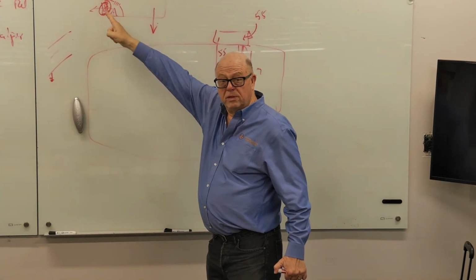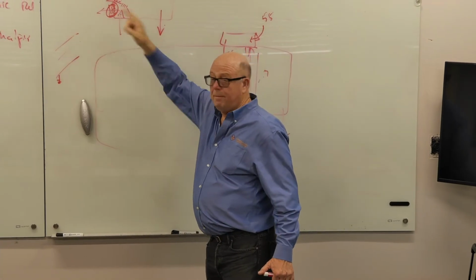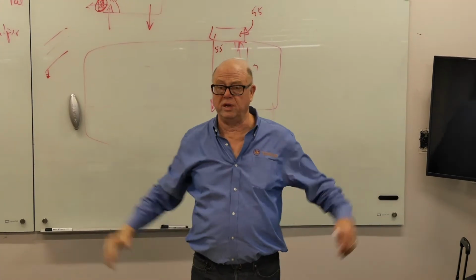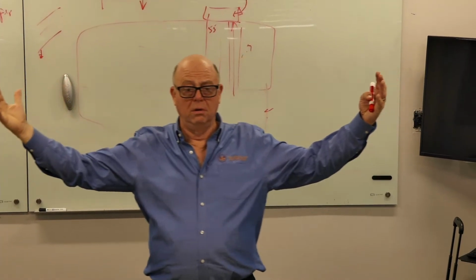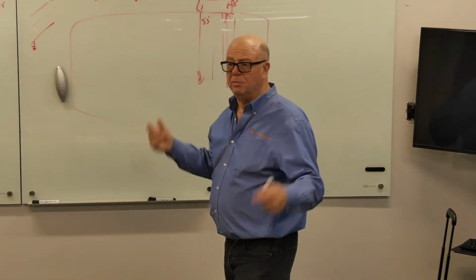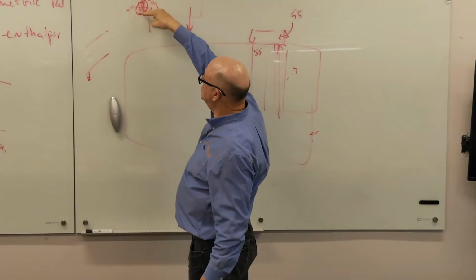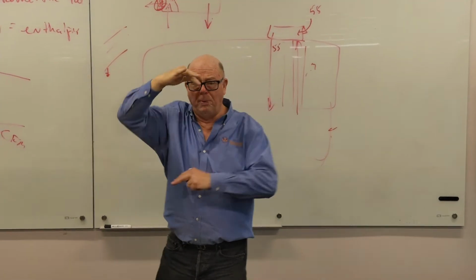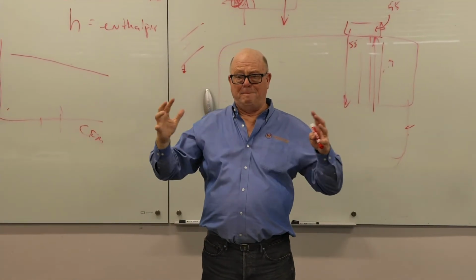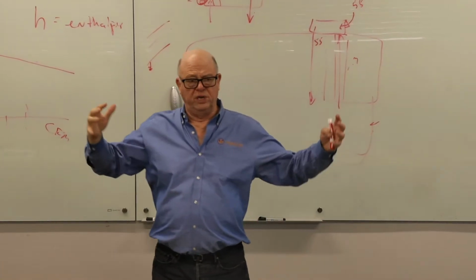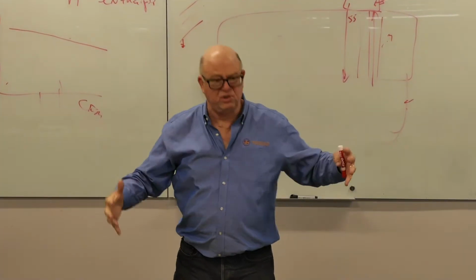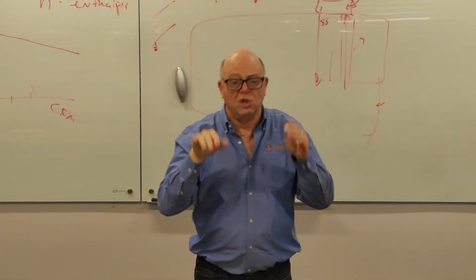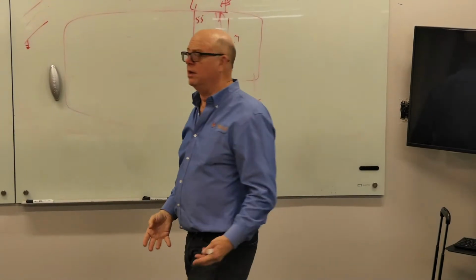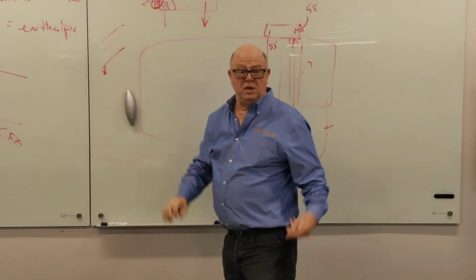Carrier recommended that for 15 tons and larger, you use that prop fan thing instead of a barometric damper, even on a 1-story application. Too much air to move. The issue was the size of that damper opening; they couldn't make it big enough on a 15, 20, 25, 30 ton unit. There just wasn't physically room to keep the velocity through it low enough that there wouldn't be a lot of static. So they recommended it needed the little fan assist.